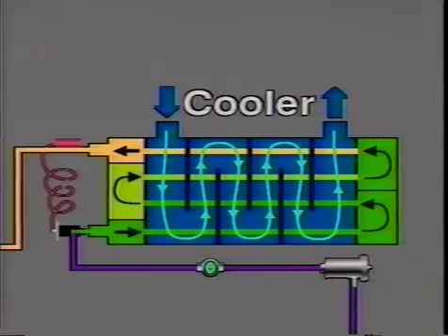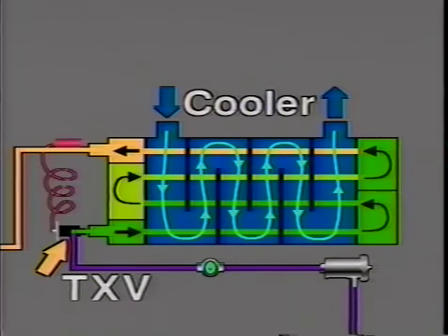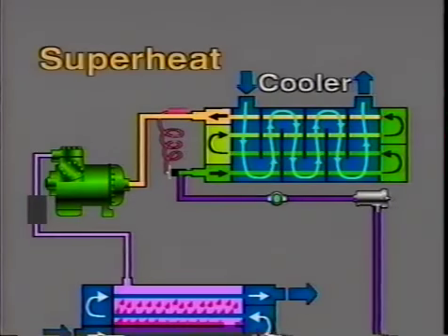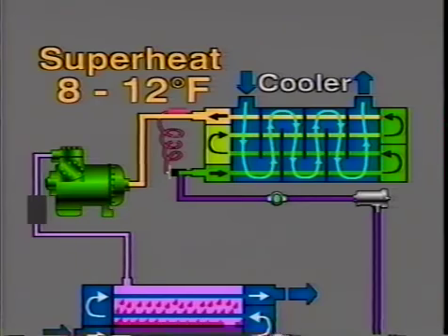Refrigerant is supplied to the cooler from the thermostatic expansion valve, which is set to provide the desired superheat leaving the cooler or entering the compressor. Some superheat is necessary to prevent damage to the compressor from liquid refrigerant, but it's desirable to keep superheat as low as possible in order to get maximum cooler capacity. Traditional systems will have 8 to 12 degrees Fahrenheit superheat leaving the cooler.